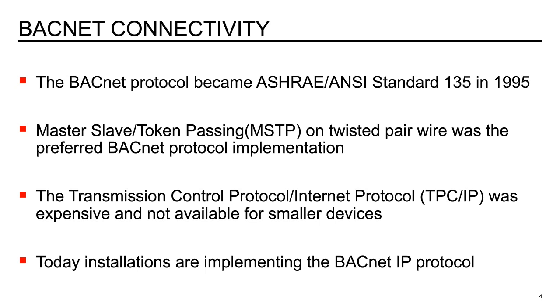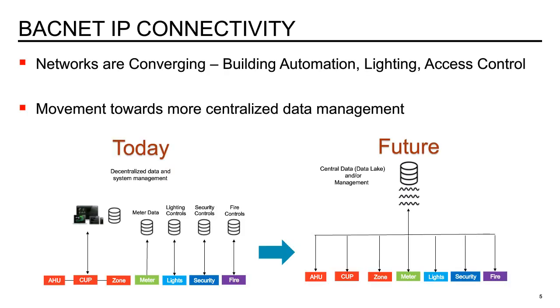And traditionally, we have seen Master Slave Token Passing, or MSTP, on twisted pair as a preferred BACnet protocol implementation. And a lot of that was due to the fact that BACnet IP, or the transmission protocol, internet protocol, was expensive and not available for smaller devices. But today, installations are implementing the BACnet IP protocol. So BACnet over IP is becoming more popular today because the cost of implementing BACnet IP has come down.